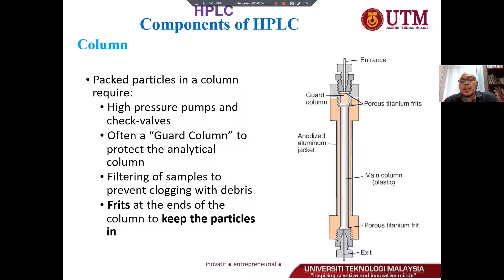So instead of replacing the analytical column, we replace the guard column. That's why, if we have a problem with, for example, a splitting peak or what we call a column void, the first thing we try is to change the guard column. The guard column is not that expensive compared to the analytical column. An analytical column will cost you about 1,500 to 3,000, but the guard column costs only about 500. So instead of wasting 2,000, we can replace only the guard column. That's the thing we can try first before we replace our analytical column.